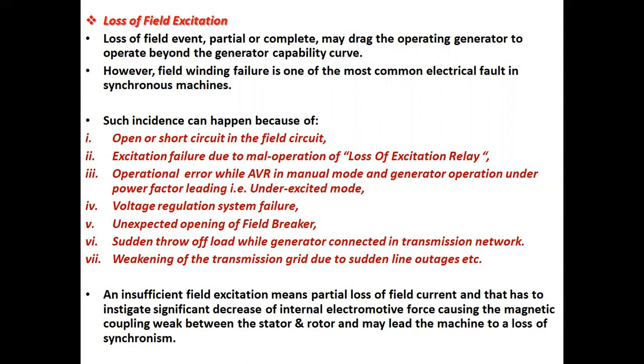Number three, operational error while AVR is in manual mode and generator operation under power factor leading, that is under excited mode. Number four, voltage regulation system failure. Number five, unexpected opening of field breaker. Number six, sudden throw off load while generator is connected in transmission network. Number seven, weakening of the transmission grid due to sudden line outages, etc.